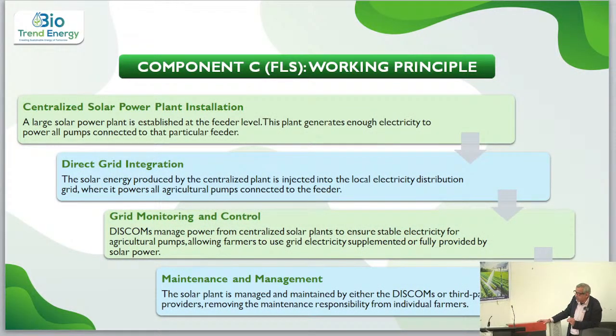So the working principle here is you have a centralized solar power plant installation, a large solar power plant established at the feeder level. The plant generates enough electricity to power all pumps connected to the particular feeder. All pumps on the feeder will get connected. Direct grid integration: solar energy produced by the central plant is injected into the local electricity distribution grid, where it powers all the agriculture pumps connected to the feeder. Grid monitoring and control system: the discom manages power from the centralized plant. So ultimately, it's the discom which is responsible for the facility. The centralized solar power plant ensures stable electricity for agriculture pumps, allowing the farmer to use grid electricity, supplemented or fully provided by solar power. And maintenance is generally done in these cases by the discom, because it's a central facility. So the individual farmer need not worry about it, or about a third party or vendor who has set up this facility.